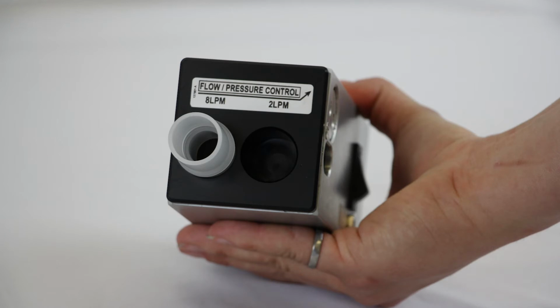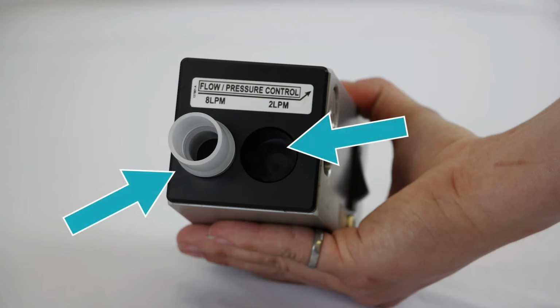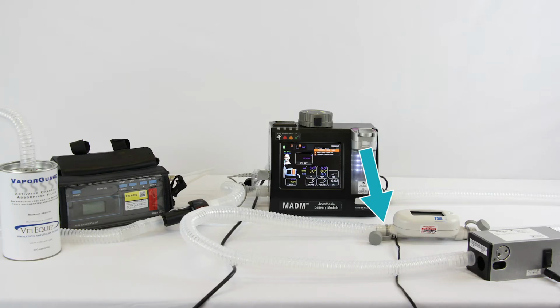To set up for the operational test, connect one piece of patient tubing to the patient sensor circuit adapter connected to the adjustable flow source in either the 2 liter per minute port for low flow testing or the 8 liter per minute port for higher flow testing. Connect the other end of the patient tubing to the flow meter. Use a second piece of patient tubing to connect the flow meter to the inlet sensor on the right side of MADM.